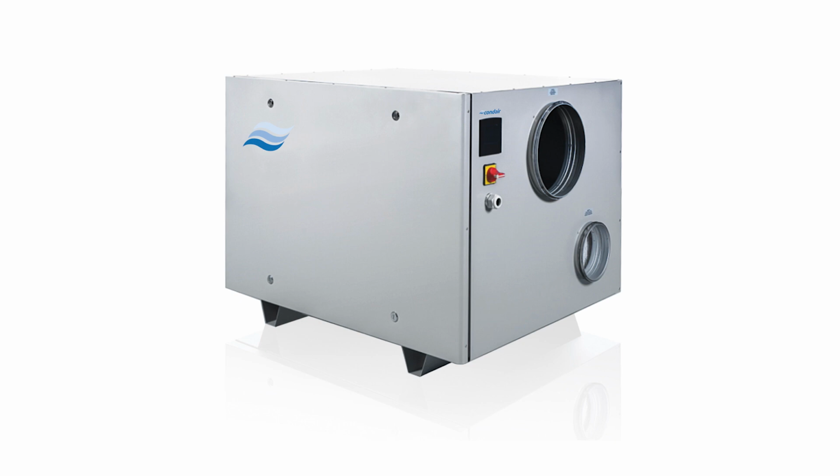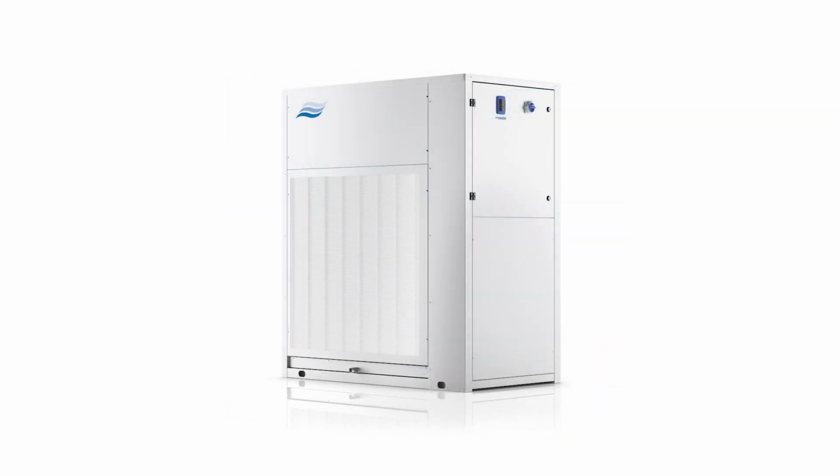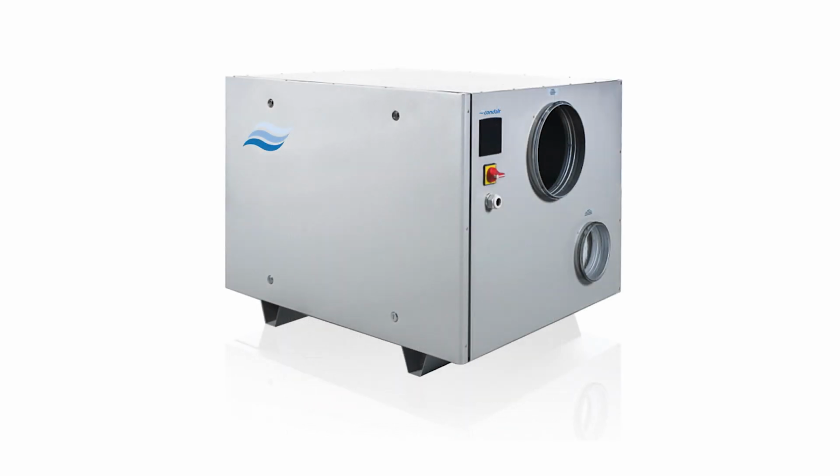If this heat gain causes an area to overheat, people in the room will often just open windows to let the heat out. But this causes problems as that lets more moisture in, which negatively affects the humidity control. And we can combat this heat gain in a condensing project by using an external condenser unit, very similar to split air conditioning units, where the external condenser part sits outside. And in the desiccant systems, cooling modules can be attached after drying to bring the supply air temperature back down.